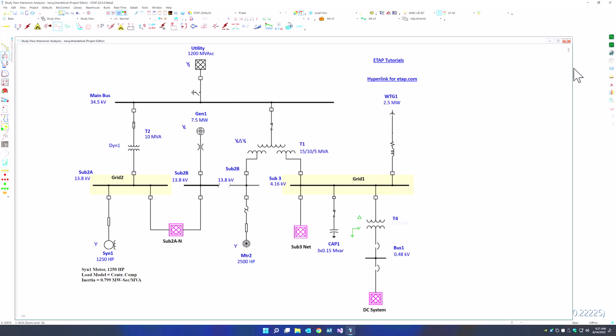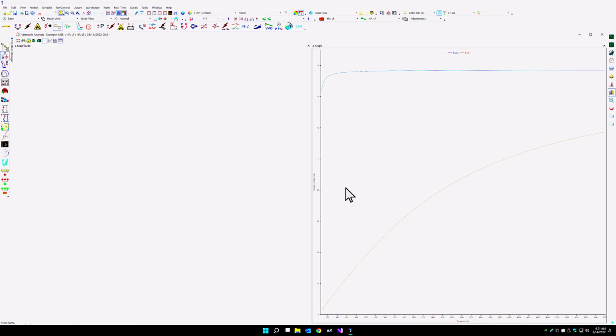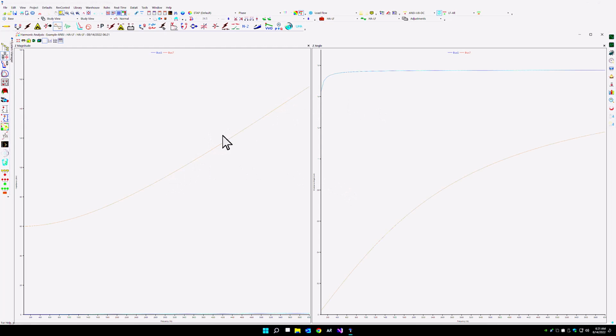The harmonic analysis zero sequence scan is selected from the study case, so you can choose between the existing positive sequence or switch over to the zero sequence network and run the frequency scan. And as usual, ETAP will show you the impedance at the one line diagram level.